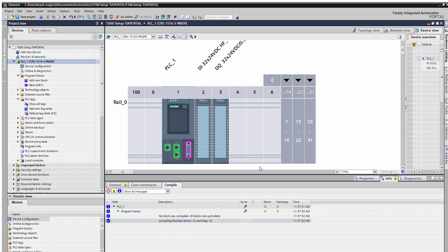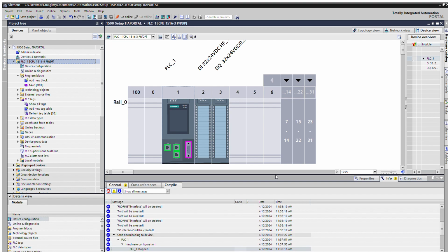Now this particular one is software synchronization. Basically, what this is saying is that the items that are here, that are part of the software, are not the same as what's currently in the PLC. So all you're saying is agree and continue without synchronization, so you're not trying to match them up. And then sometimes, depending on who was last at the PLC, you may have to do a stop all here. Currently we're fine, so we can just press load. Once this finishes, we'll be able to press finish and that will reboot the PLC with the newly installed software. So press finish, and I can see the PLC behind me is booting up and goes back into run mode.